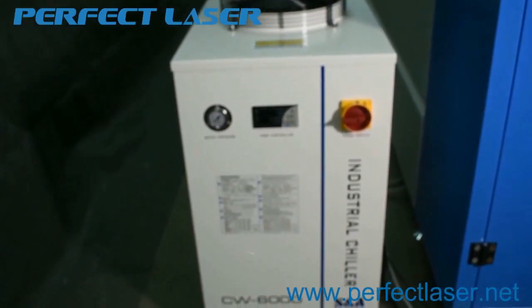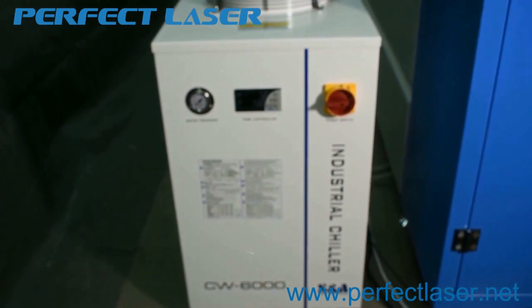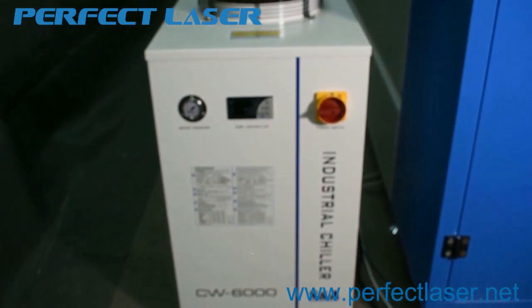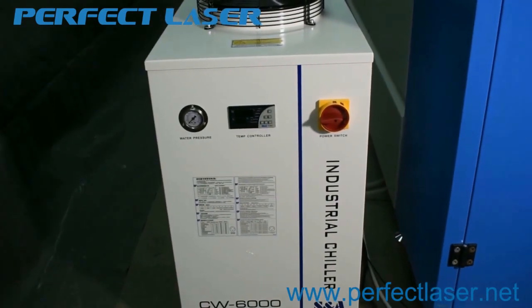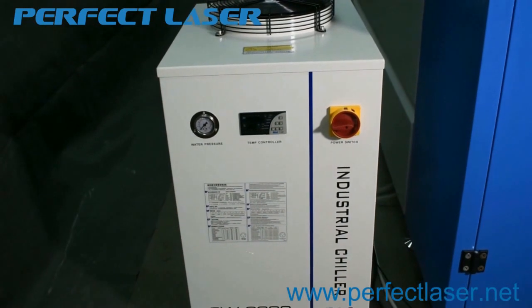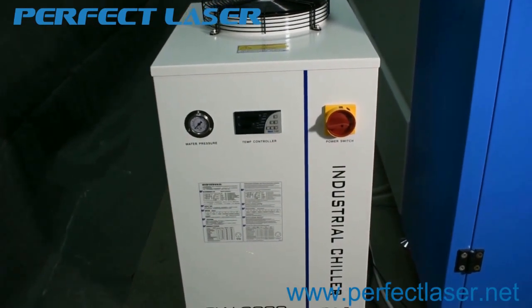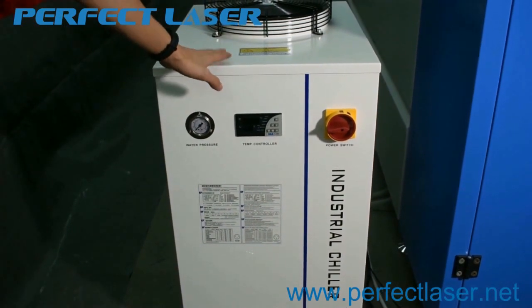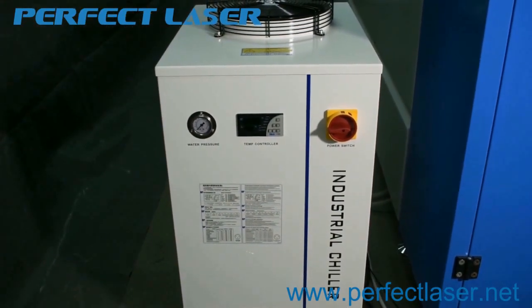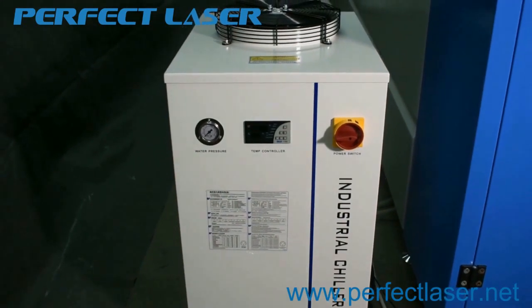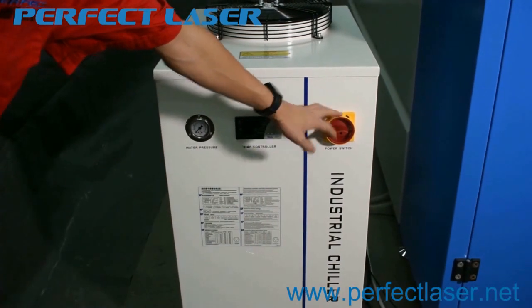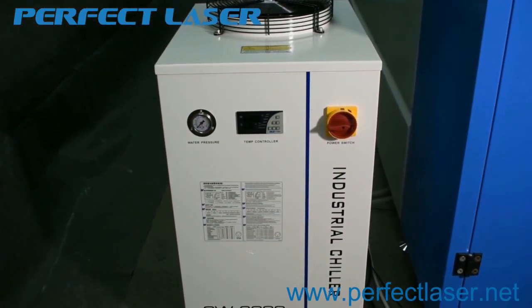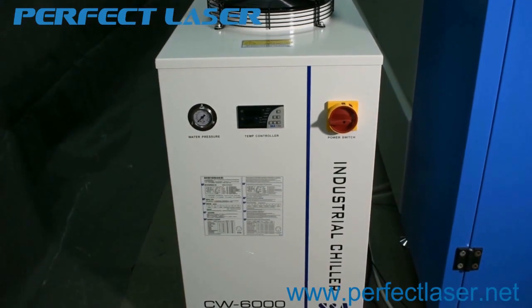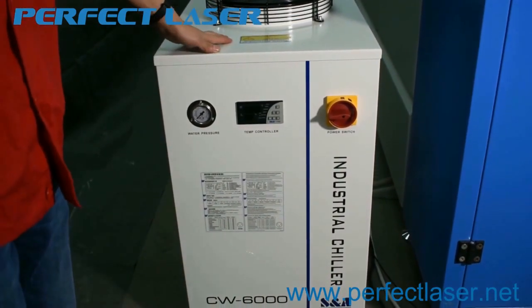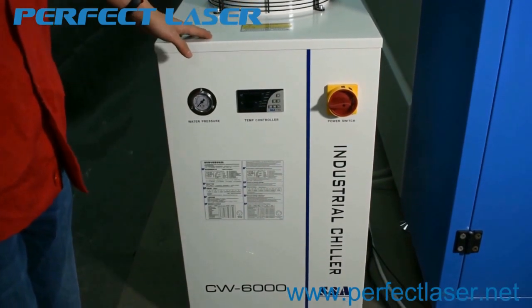This uses 220 volt single phase power. We use the water chiller to cool down the heat in the laser tube, and the water chiller's voltage is 220 volts, 50 Hz, single phase. The water chiller's power switch is on the machine. The power supply for the water chiller is connected into the laser machine, so there's no need to turn on the red button separately. The key switch will control the water chiller automatically.